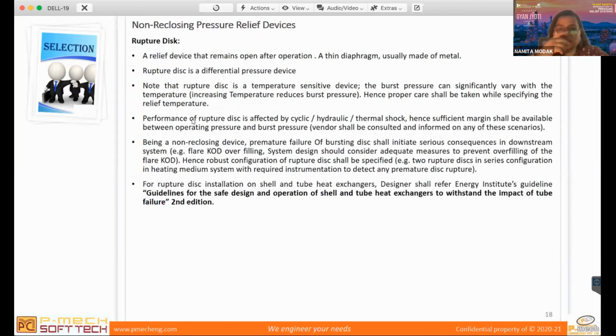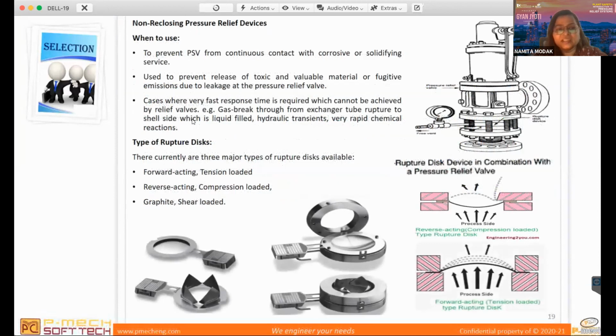A rupture disc is a non-reclosing type of equipment. Mainly we go with a rupture disc when the fluid is corrosive, so you don't want your PSV in corrosive or high temperature service. In that scenario we use a rupture disc. Sometimes you give the rupture disc in combination with a PSV, because a rupture disc is not considered a reliable safety for your system. These are the different types of rupture discs available in the market: forward acting, reverse acting, and graphite shear loaded.